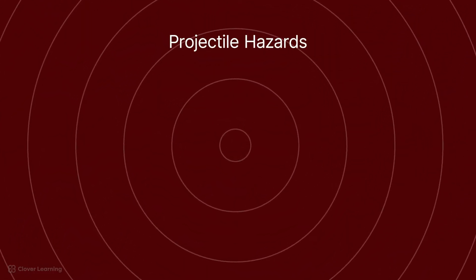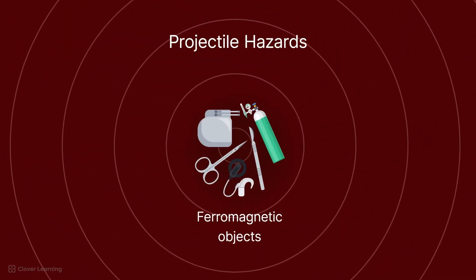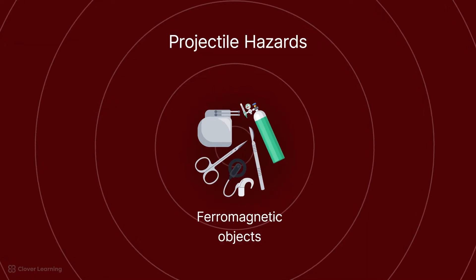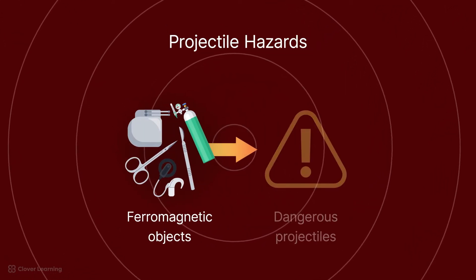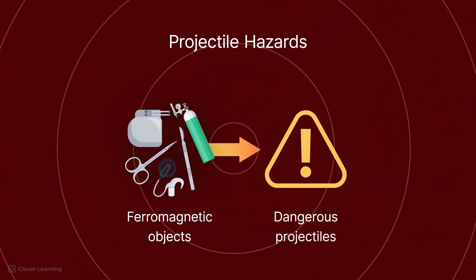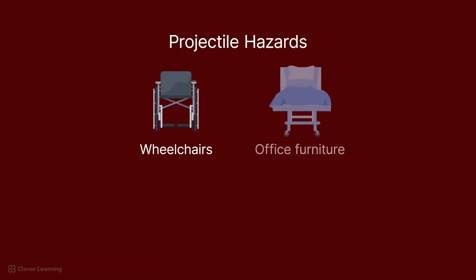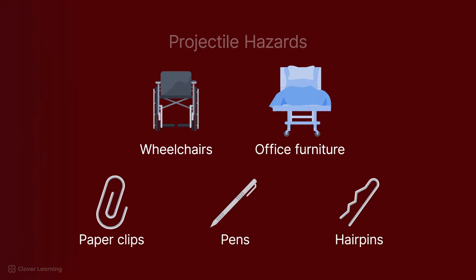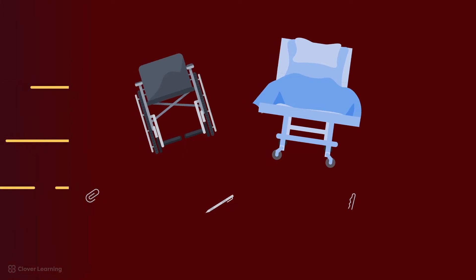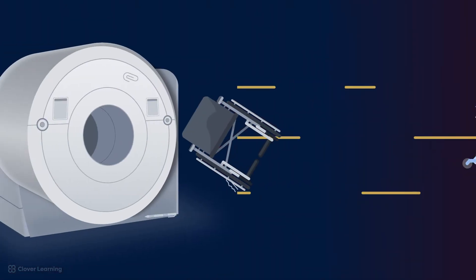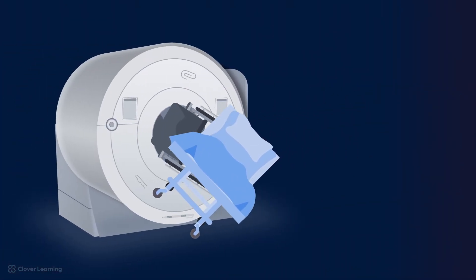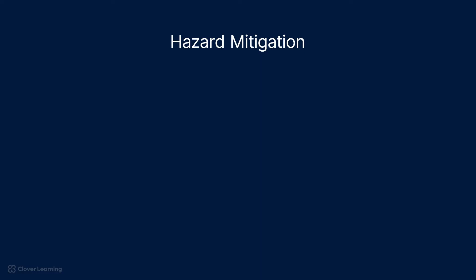Next, we need to discuss the hazards of projectiles in the MRI environment. The powerful static magnetic field can turn ferromagnetic objects into dangerous projectiles. These dangers include obvious threats such as wheelchairs and office furniture, and small objects that a technologist might not notice, like paperclips, pens, or hairpins. Any of these items could cause serious injury if they are drawn into the magnet.